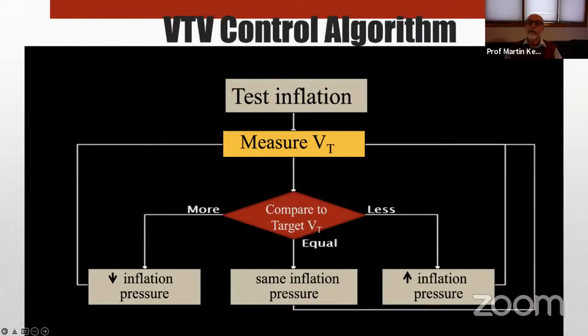But now we have a more sophisticated approach, which is what I refer to as volume targeted ventilation. There's some confusion in the literature. Some people refer to volume targeted ventilation as anything that pays attention to tidal volume. But the way I use it is pressure controlled ventilation with automatic adjustment of inflation pressure. So it's still pressure controlled, but instead of manual adjustment of the inflation pressure, we let the ventilator make those adjustments automatically and in real time. So after an initial inflation or two, the tidal volume is measured. It's compared to the target, and if the tidal volume measured is less than target, inflation pressure will go up for the next cycle. If it's within a few percent of the target tidal volume, no change. And if it's above the target, the inflation pressure will be reduced for the subsequent cycle.